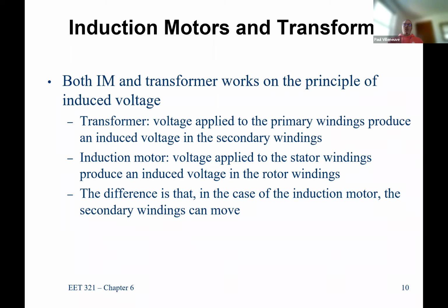Except, and I learned this a long time ago, 20 years ago, is there an application when you would want to keep the motor energized regardless of how much current it was pulling through? It can never exceed what we would call the blocked rotor current demand. Would you ever want to provide the protection? Because remember, that piece of equipment is getting hot. What type of application for an induction motor would you perhaps want to allow a blocked rotor current to go indefinitely? Anybody want to guess?